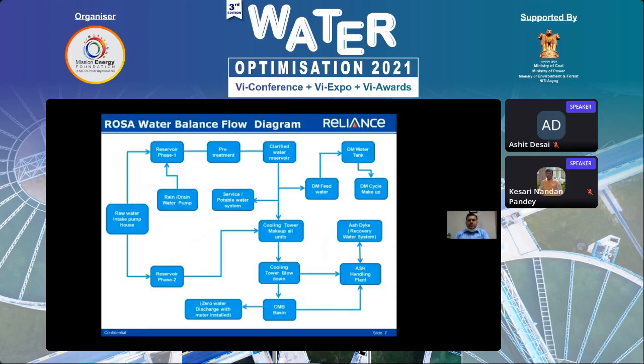So what is the intake of the water and what is the outcome of the water should be nullified, so that we can manage zero water wastage here. We have the intake pump here, which is 1 kilometer away from the plant. We have 2 reservoirs here. The water goes to the pre-treatment and clarifier system with the DM water circuit in place, and then from the clarified water, a cooling tower makeup.